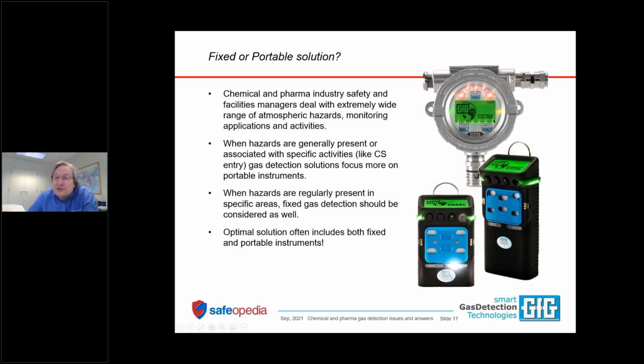As I mentioned, the solution can be either fixed or portable, or a combination of fixed and portable. When the hazards are generally present everywhere all the time, like at a petrochemical plant, typically you'll have every worker in that area on the chemical plant side of the refinery equipped with either minimally a single channel H2S monitor or a 4-gas monitor that's looking for H2S, combustible gas, oxygen, and carbon monoxide.